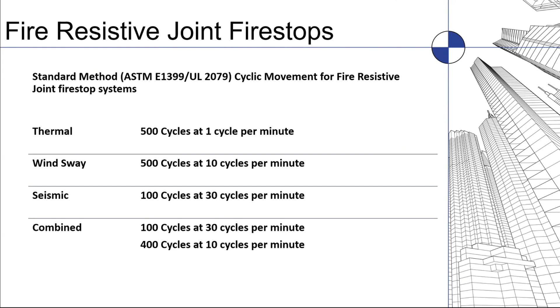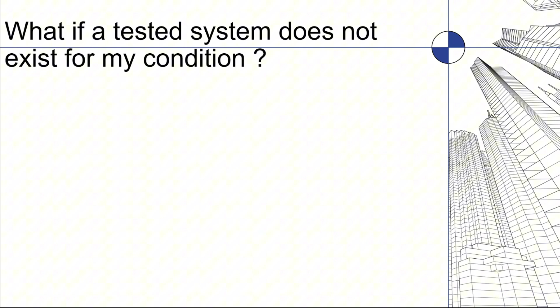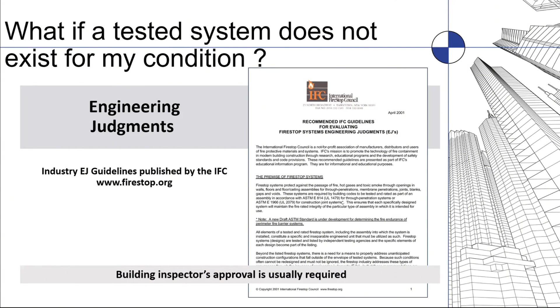So let's say you're on a project and you've got a non-conforming application - you can't find a listing anywhere that meets the criteria in your particular building. What do you do? You generally go to an engineering judgment. An engineering judgment is a guideline, and there are guidelines posted by the International Firestop Council that indicate how these judgments are supposed to take place. There are criteria that the writer of an engineering judgment must go through, and then a building inspector or authority having jurisdiction has to approve the application.